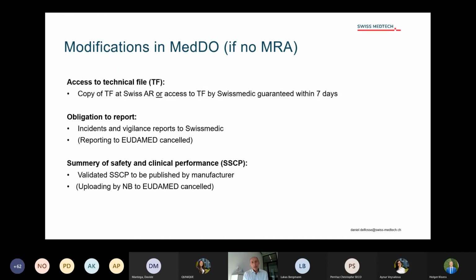We also have some technical aspects in the medical device ordinance, such as the access to the technical file. You either have a copy of the technical file at the Swiss AR, which is basically what Europe asks of the European rep, or you can guarantee access to the technical file by Swissmedic if they ask for it within 7 days. You have an obligation to report incidents, vigilance reports, to Swissmedic and not to Eudamed, because that is not possible if there is no MRA.